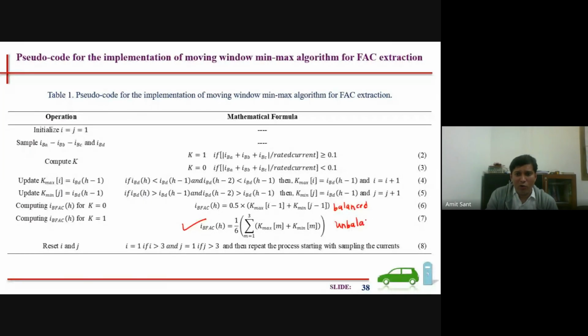But how to know what is balanced and what is unbalanced? We can add the 3 currents and find out how much unbalance is there - whether unbalance is there or not. The other thing is what is the degree of unbalance, how much percentage unbalance. Based on that, your algorithm changes. So this adds to the complexity.